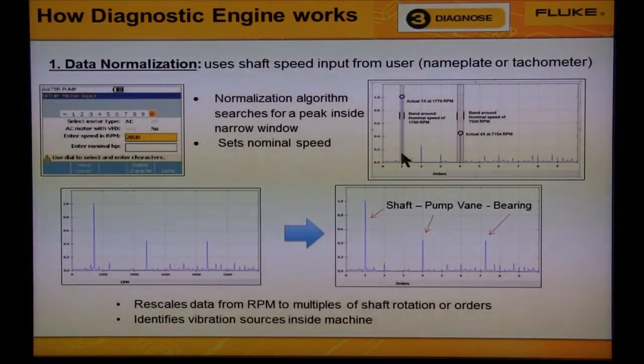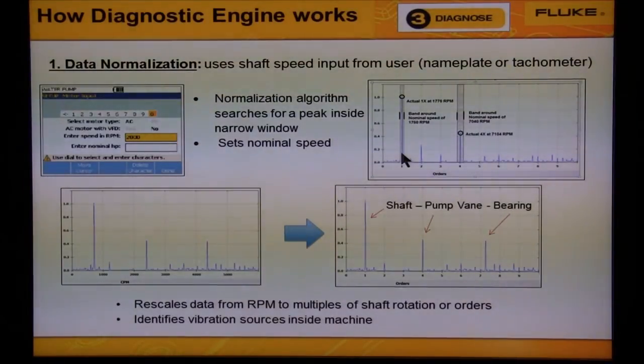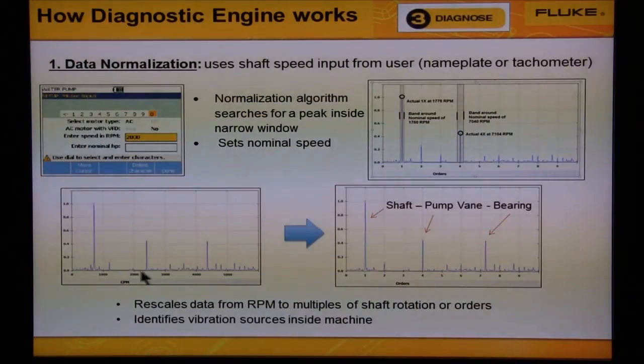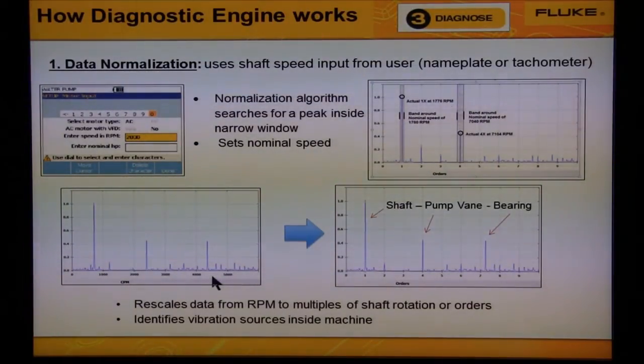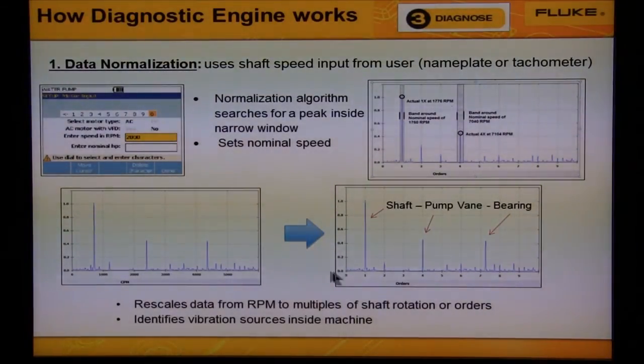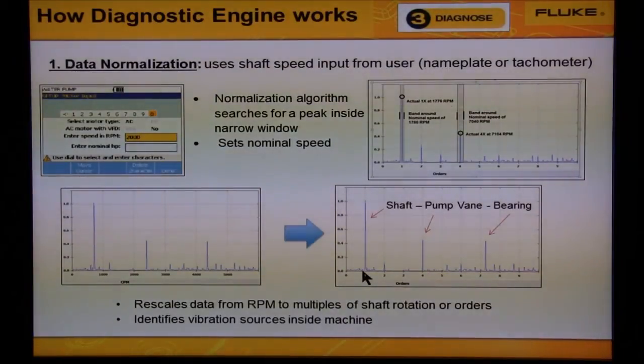The largest vibration typically comes from the large heavy mass of metal rotating at, say, 600 RPM. In the graph on the bottom left, we see a peak at 600 RPM, a peak at 2400 RPM, and a peak at 4500 RPM. The diagnostic engine is told that the machine speed is 600 RPM and identifies the peak at 600 as the vibration from the rotating shaft, as seen on the graph on the right.